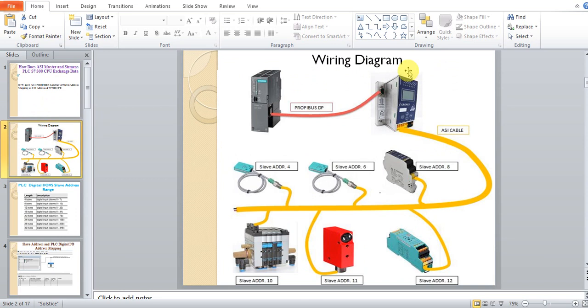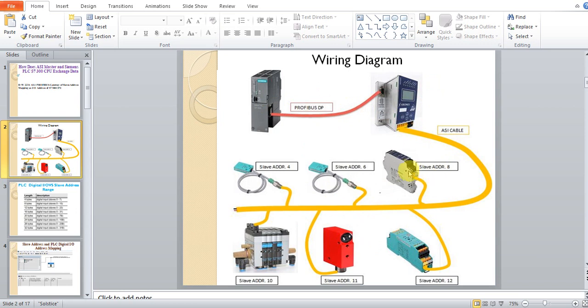The wiring diagram looks like this. Here is the S7 CPU, and here is the AS-i master. Those are the slaves. The CPU is connected to the AS-i master by Profibus, and the sensor-actuator slaves are connected to the AS-i master by the AS-Interface cable. As you can see, the addresses are included on the sensors.